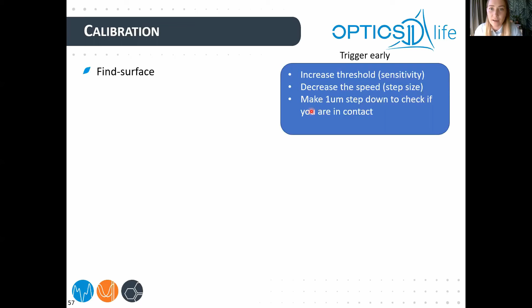Now, if the find surface step triggers early, you need to increase the threshold in options, or if you have old hardware, it's called sensitivity. You also can decrease the speed, because movement of the piezo also induces some noise. Or in old hardware, that's the step size, so moving at smaller steps gives less noise. And you can check manually as well the 1 micrometer steps if you're really in contact or not.